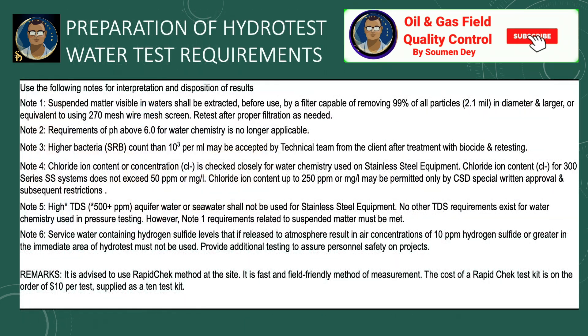Use the following notes for interpretation and disposition of results. Note 1: Suspended matter visible in water shall be extracted before use by a filter capable of removing 99% of particles 2.1 mil in diameter and larger, or equivalent. Note 2: The requirement of pH value above 6.0 for water chemistry is no longer applicable. Note 3: Higher bacteria SRB count than 10³ per milliliter may be accepted by the technical team from the client after treatment with biocide and retesting.